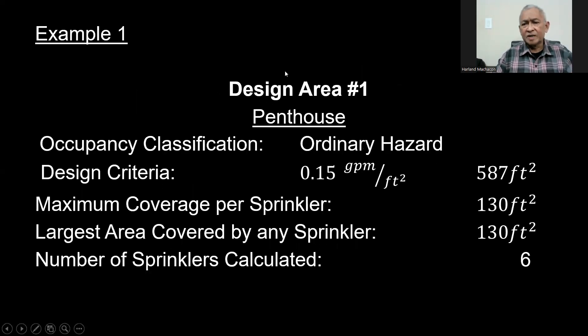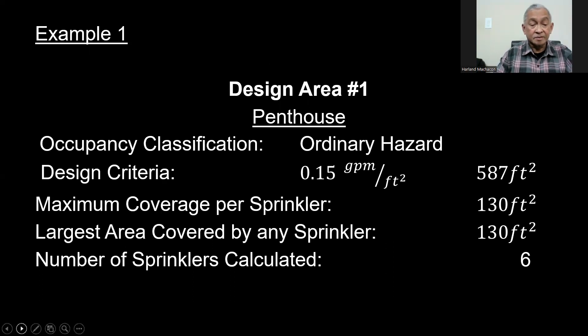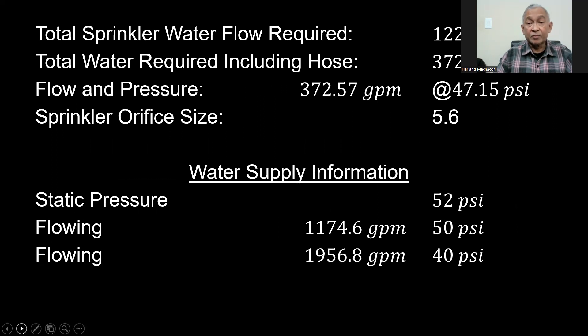Based on our previous calculations on fire sprinkler demand, we get this data here. We have a design area, which we call design area number one, which is a penthouse. It is classified as ordinary hazard with a design criteria of 0.15 gallons per minute per square foot and 587 square feet. Maximum coverage per sprinkler is 130 square feet, and the largest area covered by any sprinkler based on our layout was 130 square feet. The number of sprinklers calculated is six.